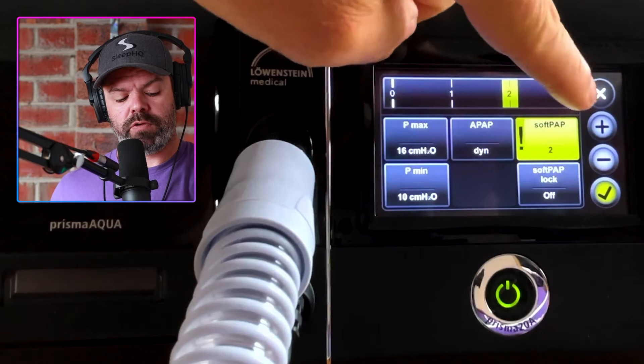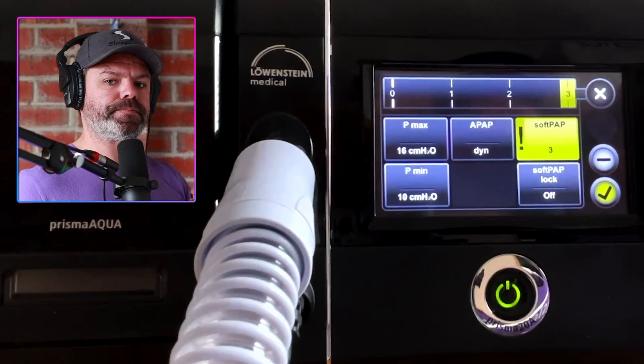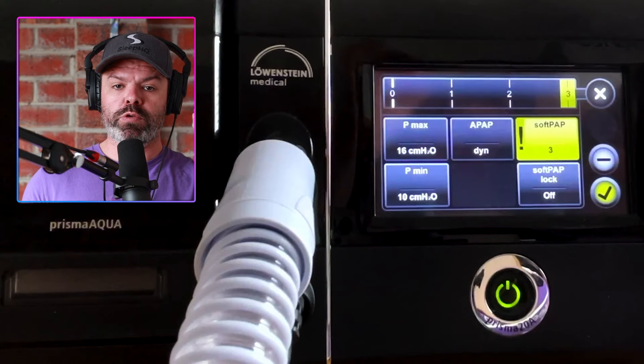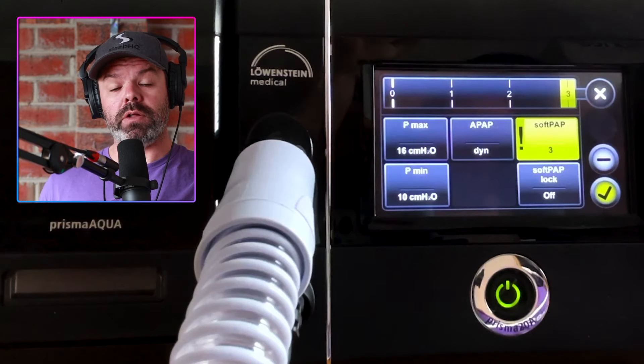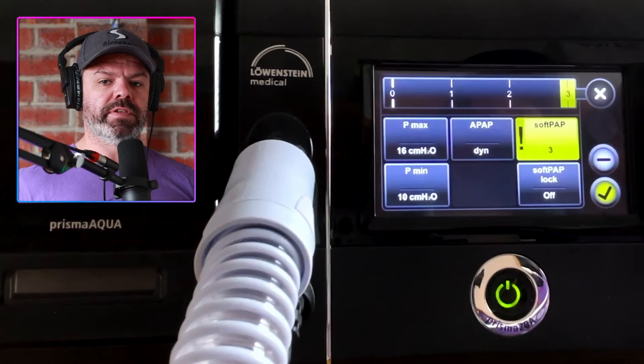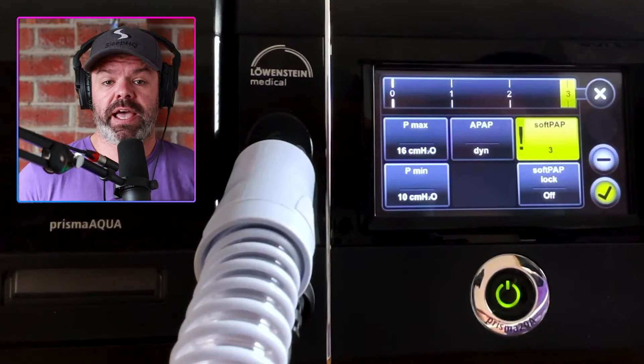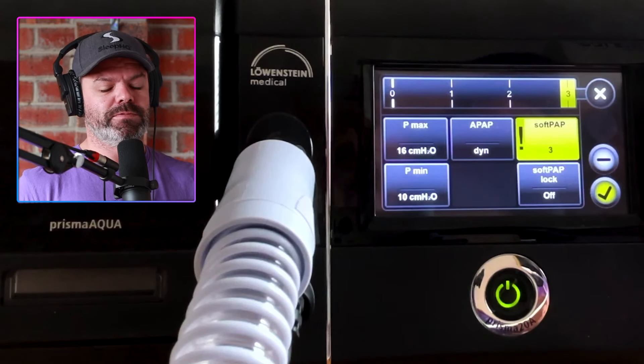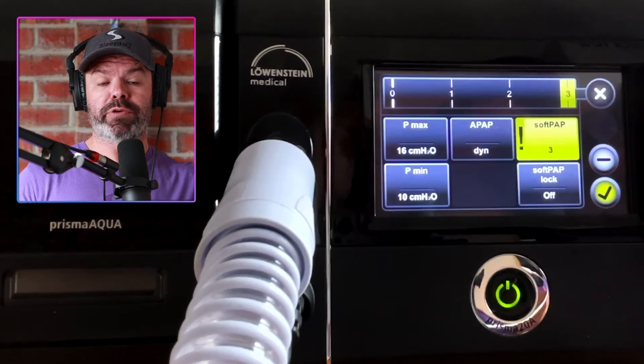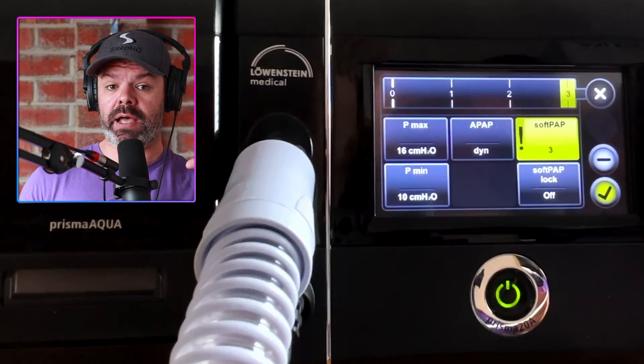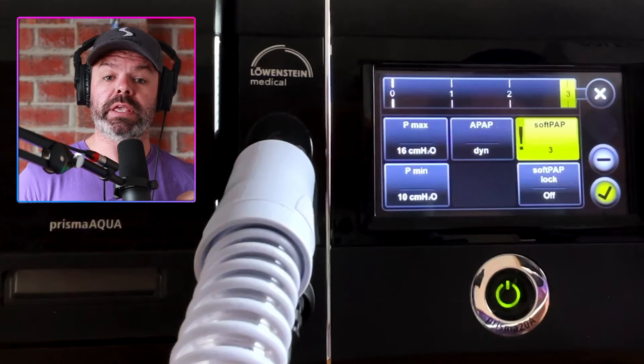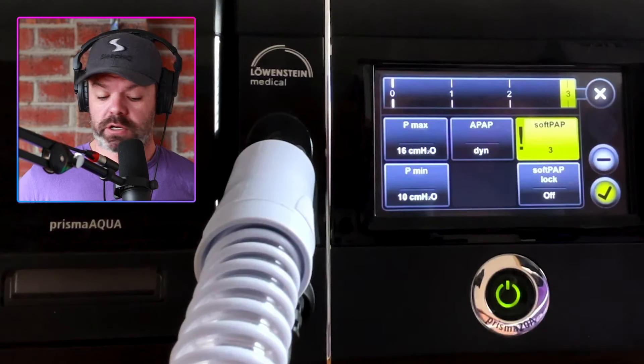At level three it changes a little bit — yes, it gives you a moderate level of pressure relief as you exhale, but it also gives you a burst of pressure on the inhalation, a little bump. This is really handy for people who have that suffocation feeling at lower pressure levels. Level one and two are great for higher pressure levels when it's difficult to exhale, but level three gives you that little bump on inhalation.